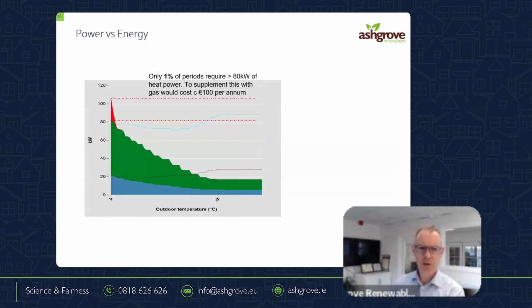Right? So, and we would do this quite a lot. And again, the software will tell us what the cost of undersizing it is. So in this case, we've put in that the load here is whatever that is, 105 kilowatt. So it's a heating load with a base load of hot water. In this case, it's 16 or 17 kilowatt, whatever it is, flat load of hot water. And in this case, we've chosen an 82 kilowatt heat pump. So two things are going to happen.